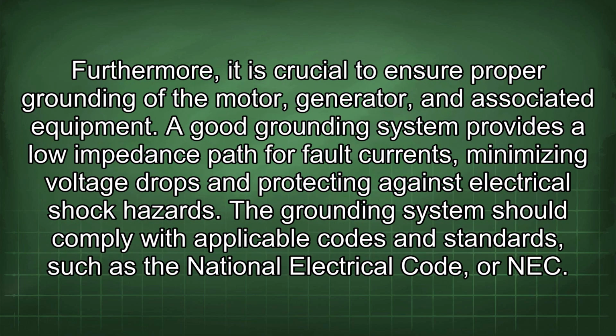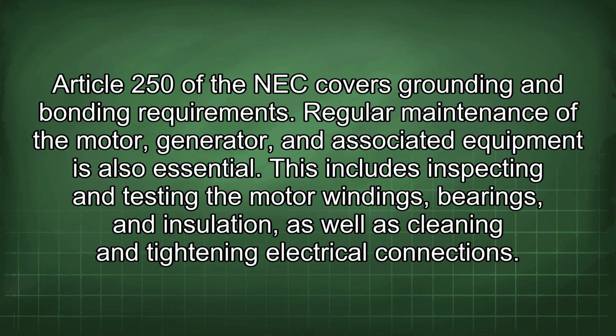Furthermore, it is crucial to ensure proper grounding of the motor, generator, and associated equipment. A good grounding system provides a lower impedance path for fault currents, minimizing voltage drops and protecting against electrical shock hazards. The grounding system should comply with applicable codes and standards, such as the National Electrical Code, or NEC. Article 250 of the NEC covers grounding and bonding requirements.